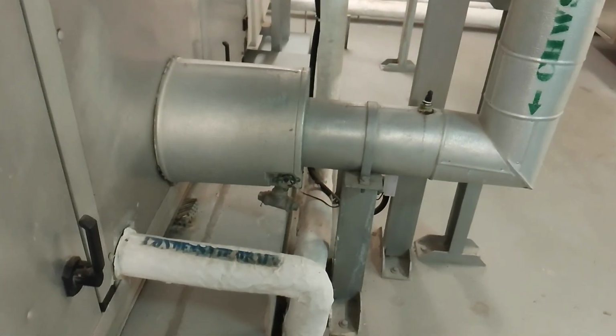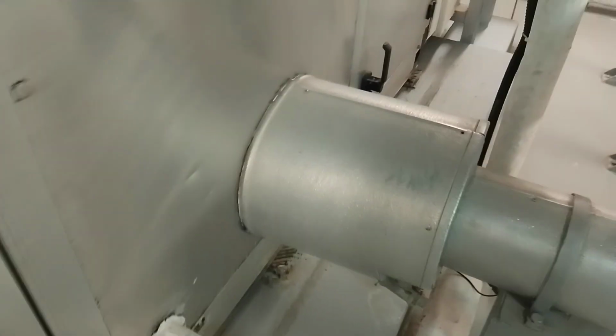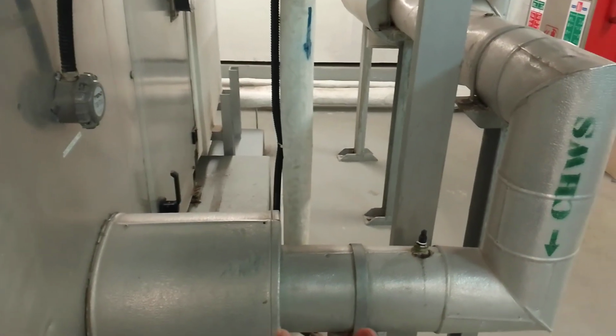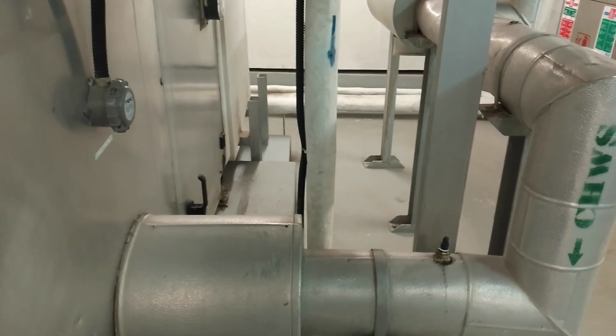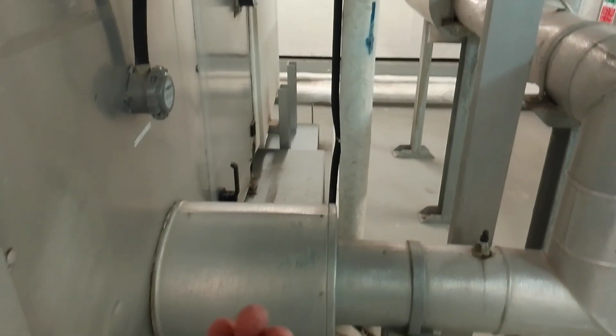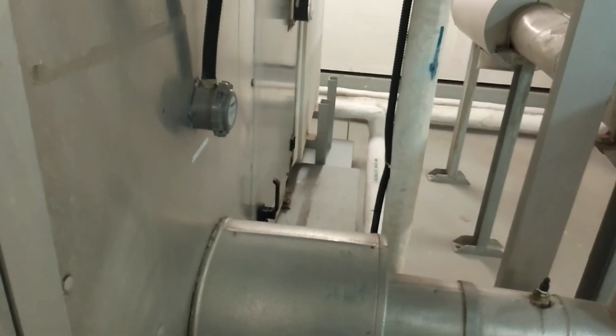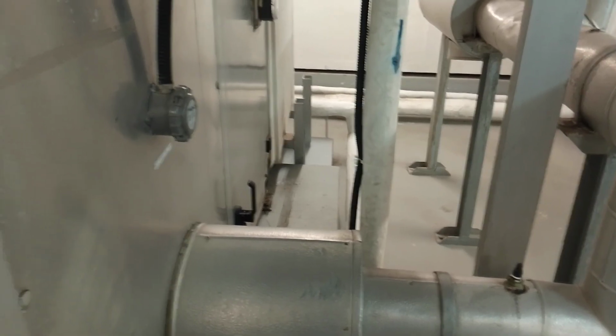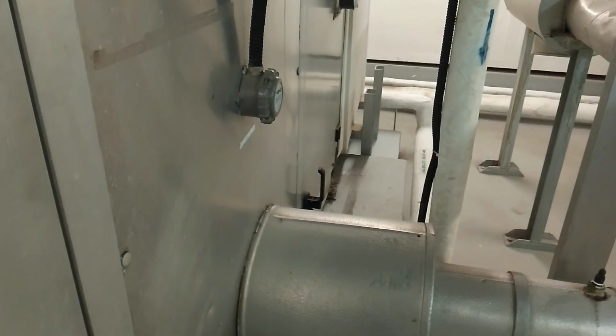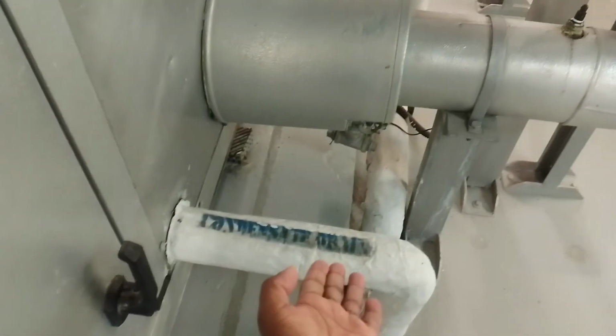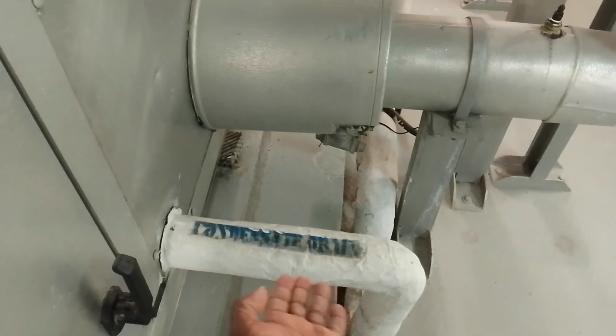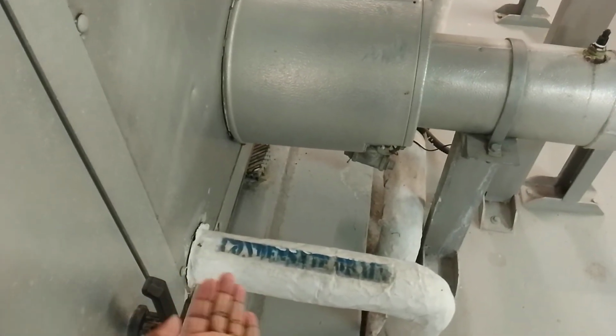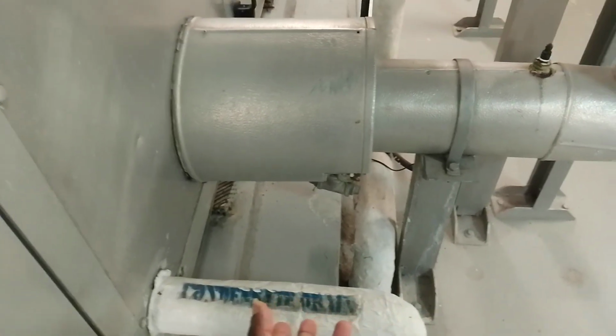Down here we have this small pipe, the white one, which is called condensate. When the water comes in, it's chilled water. So when the chilled water gets inside and meets the hot air, there is condensation, which shows as water outside. So this pipe is for discharging the water which is already condensed, to draw it out. It takes that water from the AHU outside. So that's how, and those are the things that are in the AHU.